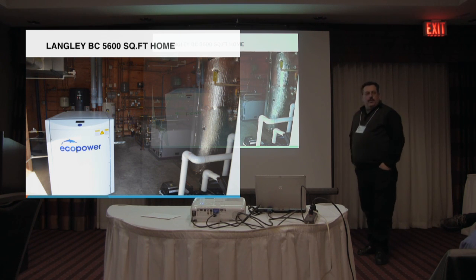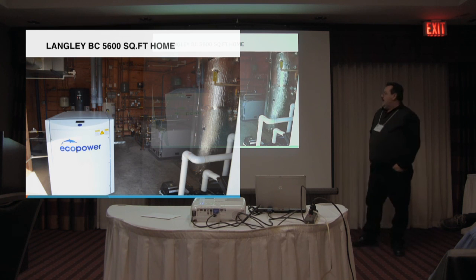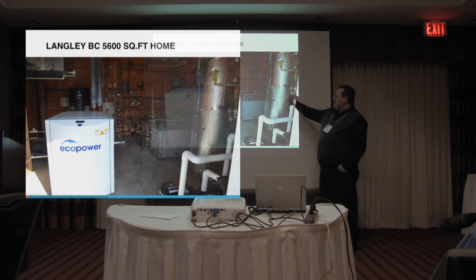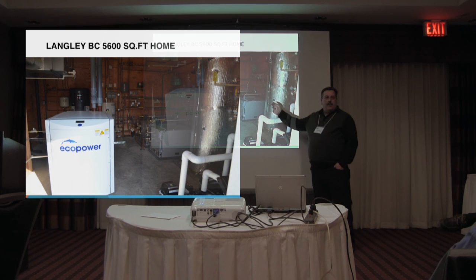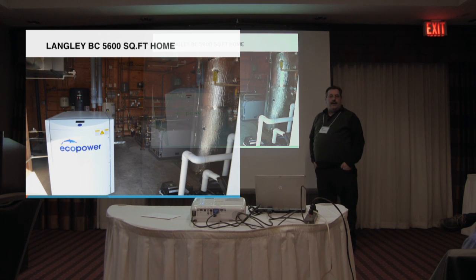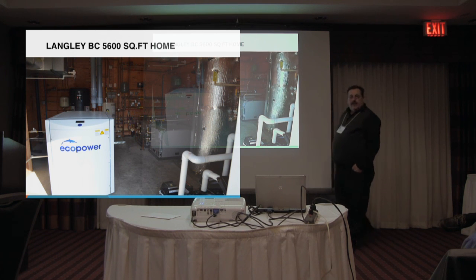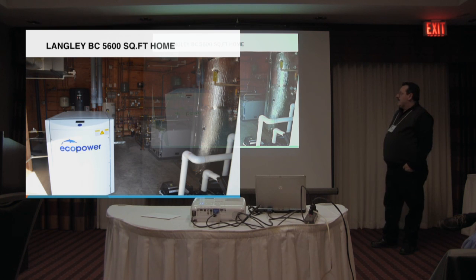So it's a very simple control strategy. And as I said earlier, there's 3 sensors in the tank. All that CHP cares about is what's happening in this tank. It doesn't care about anything else in that system. It's totally mechanically decoupled from the entire house. So very simple to troubleshoot and very simple operation.